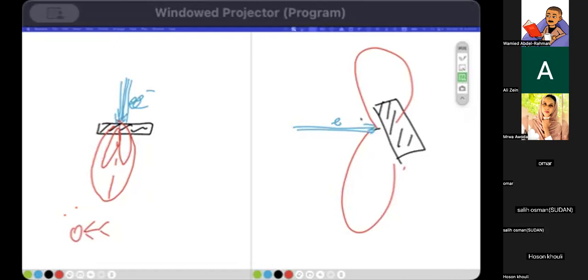We will do it for a 10 by 10 beam. If there is a deviation, usually we'll ask the engineer, please make these modifications. Try to get the beam matching the commissioning data. Otherwise, if there is an unacceptable difference, then you need to recommission everything. You will put the machine down, no treatment on it, recommission, collect the data, and so on. So I would suggest that you do an energy check. PDD can give you some sort of an energy check, quality, and so on. So there is no harm in doing this.